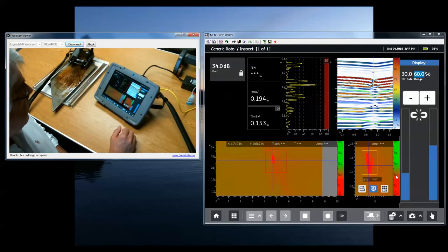What the instrument does is takes that 30% times the 0.5 inch material thickness and sets the bottom end of the palette at 150. So 30% times half an inch, 150 thousandths result. So you'll notice a pretty constant red color from 150 down to 0.